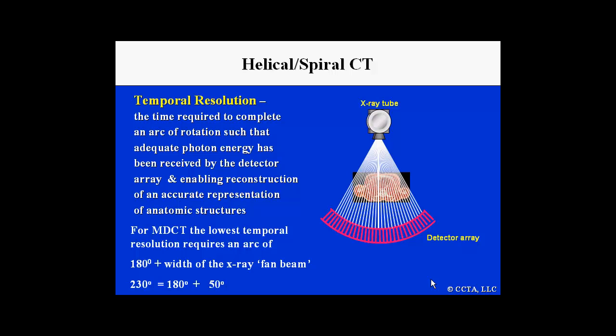For multidetector CT, the lowest temporal resolution requires an arc that includes 180 degrees plus the width of the X-ray fan beam. For a multidetector CT, this is approximately 50 degrees for the fan beam. Thus, the total arc necessary to complete an entire set of images is actually 230 degrees.